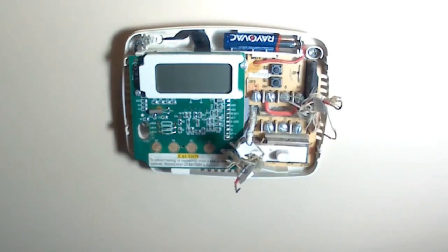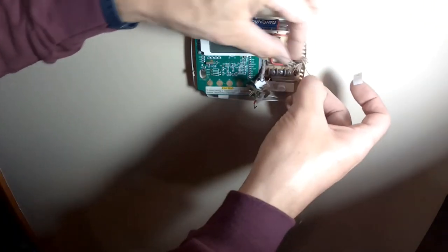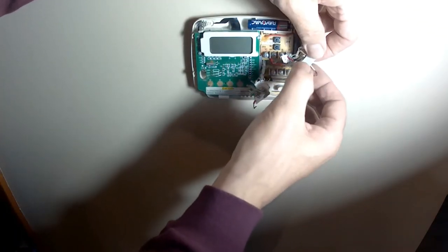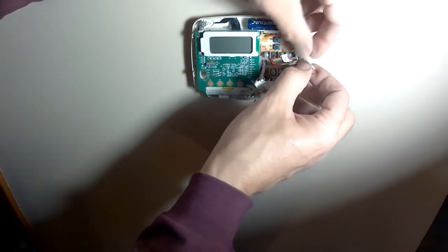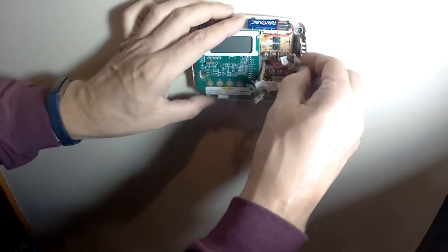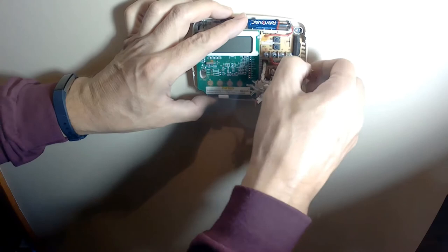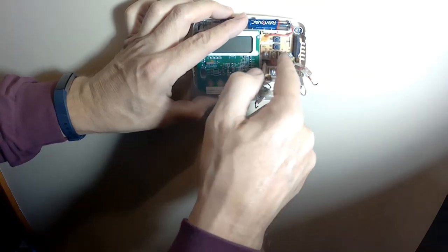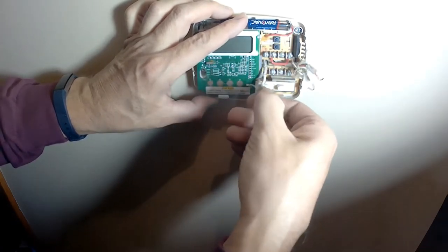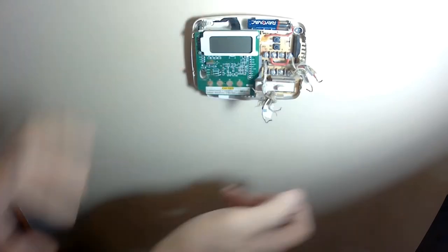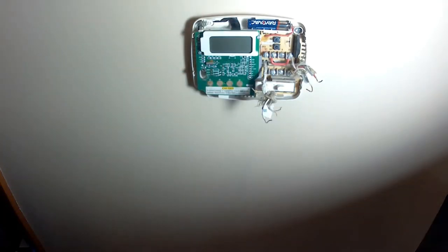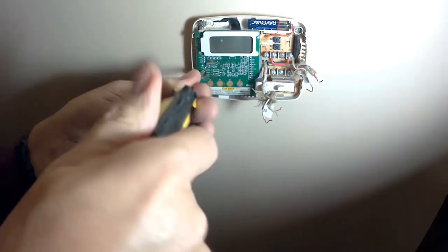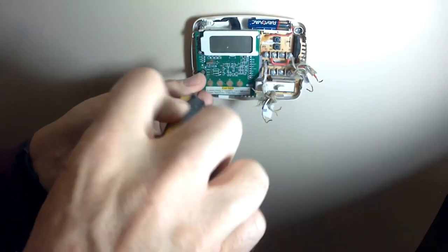Find the Y. There is the Y. Come on Y. The label doesn't want to come off. They cut too deep into the paper. There we go. Mark that wire Y. Now we got everything loose. There is a jumper between RH and RC. We are going to leave that. We are going to take the rest of the screws off so we can remove this thermostat from the wall and put the new one on.